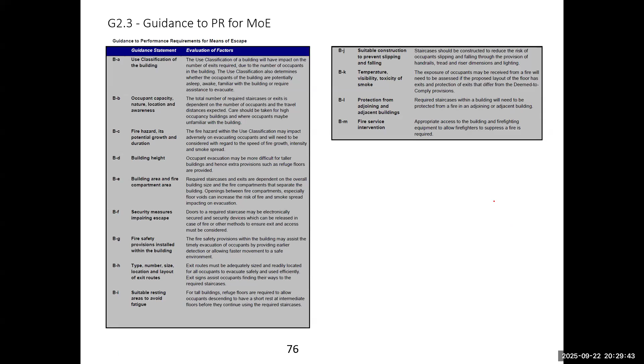Capacity and location determine the number of occupants inside the building and the number of staircases for evacuation. The travel distance, etc. We also mentioned fire hazards, which within a certain use classification may directly impact the evacuation of the occupants adversely, and need to be considered with regard to the spread of fire, intensity of fire, growth rate of fire, and smoke spread. Building height: for taller buildings, we need refuge floors to be provided. So these are some of the examples. You can read through it by yourself when you have time.